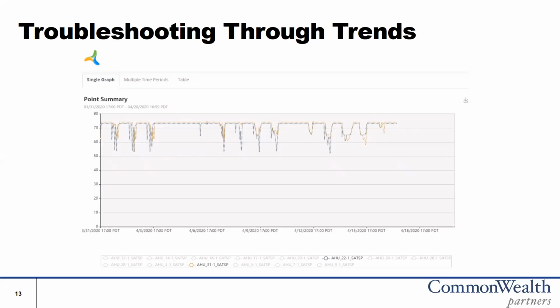We found that there was one zone where a thermostat was behind a printer, being artificially heated up, and the whole air handler was trying to ramp down to serve this one zone that wasn't actually as warm as it thought it was.